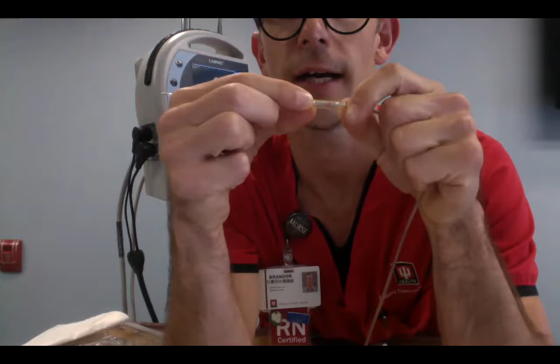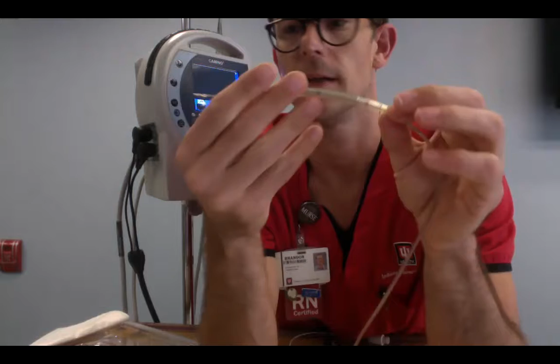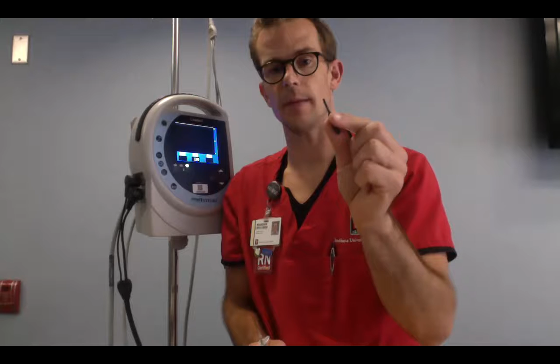And then when we come out, you'd want to call for that. Same thing over here. The newer ones have either a red dot or a black dot, and similarly, you'll see a designated window there that it has to be in between. So the neurosurgeon will set that, they will tighten it. It is zeroed. You've zeroed it with the neurosurgeon. Once the neurosurgeon has zeroed it, this probe, this cable goes into the patient's skull, and now you will never re-zero it again. Throw this in the garbage. If somebody re-zeros this while it's in the patient's skull, then it does us no good. So throw it away.